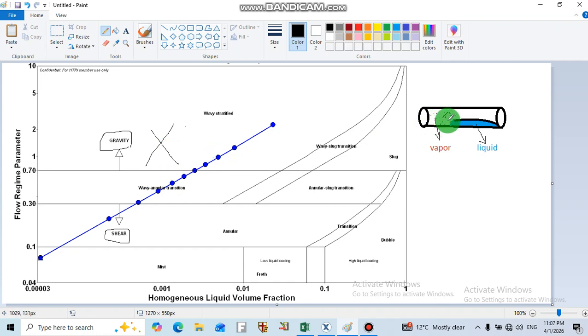In the tube side, especially when we have condensation, the typical velocity of the vapor is about 30 meters per second. I'm talking about the recommended range of velocity for the vapor and the liquid, and for the liquid we have 1 to 3 meters per second. It's really dependent on your material or piping specification or the criteria that you are working with. It's a typical value, so just take this as an example.